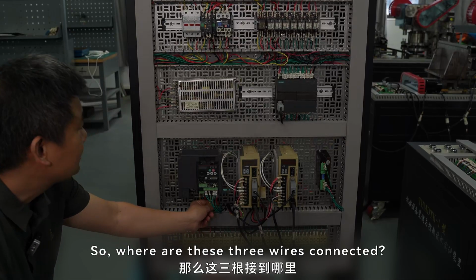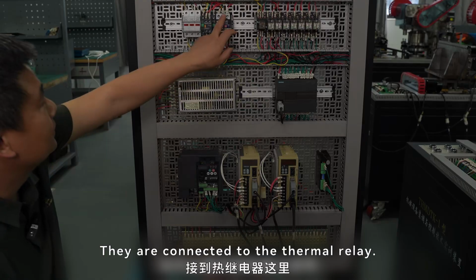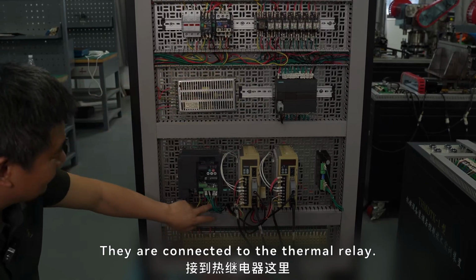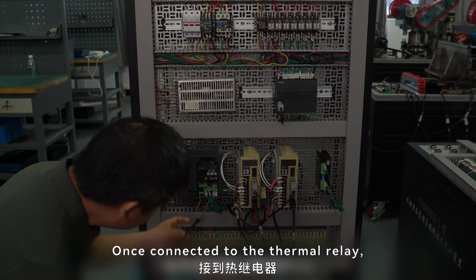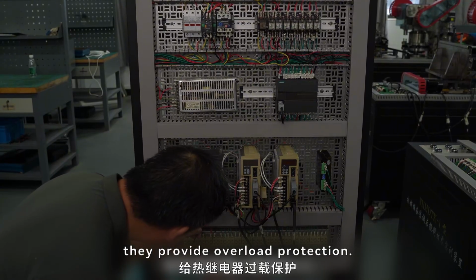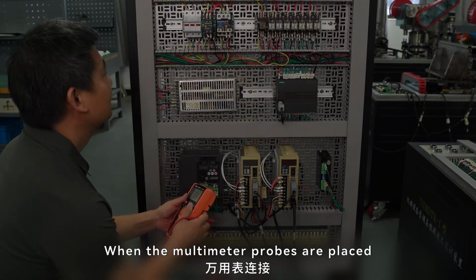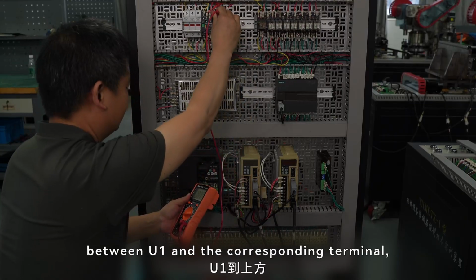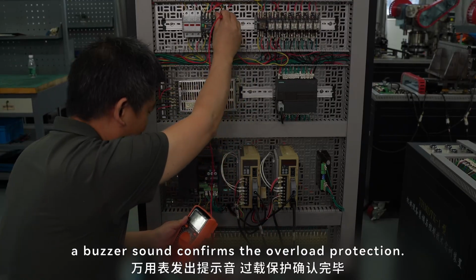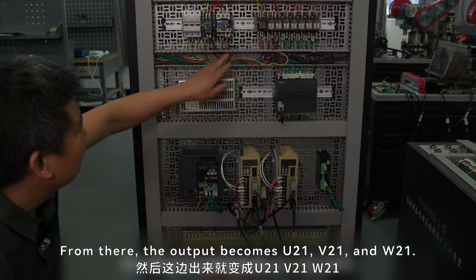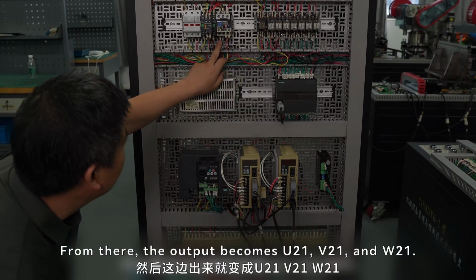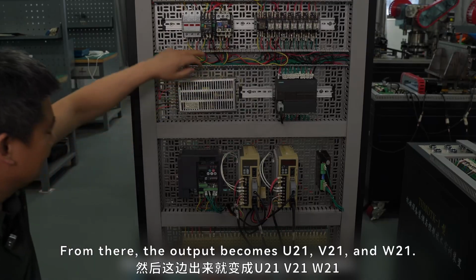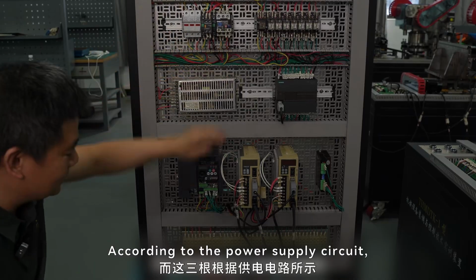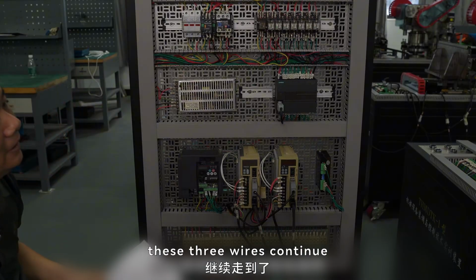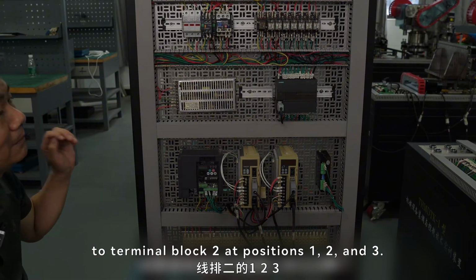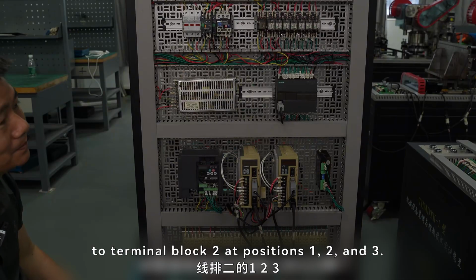So, where are these 3 wires connected? They are connected to the thermal relay. Once connected to the thermal relay, they provide overload protection. When the multimeter probes are placed between U1 and the corresponding terminal, a buzzer sound confirms the overload protection. From there, the output becomes U21, V21, and W21. According to the power supply circuit, these 3 wires continue to terminal block 2 at positions 1, 2, and 3.